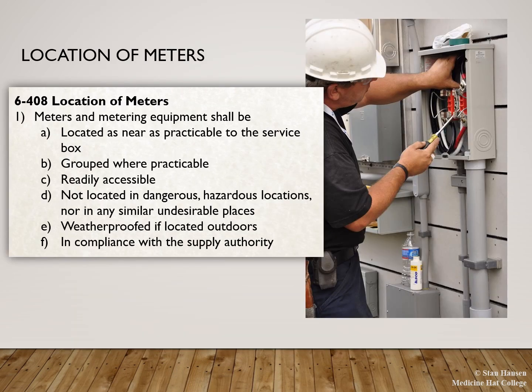Once we determine what kind of service we're going to do, we still need to make sure that we locate our meters in the proper location. Rule 6-408 tells us where we can and cannot put our meter bases. We need to make sure that they're located in the correct position, so when they enter the building, they're going to be close to the service box. We have to make sure that if we have multiple meter bases on the same building, they're going to be grouped together. They need to be readily accessible, which is in section 0 for definitions.